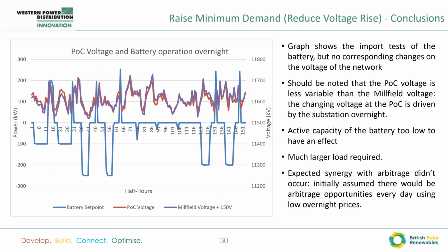So we ran the tests over several nights. This is showing several nights' worth of tests. We're looking for any obvious dips when the battery is importing. Now, the first night on the left looks quite promising, and then the second night, as we start importing, the voltage shoots up and then seems to go back down again just before we finish importing. I've boosted the voltage at Millfield by 150 to match the POC voltage, because there is a voltage drop across that feeder. And this way the changes in voltage can be directly compared.